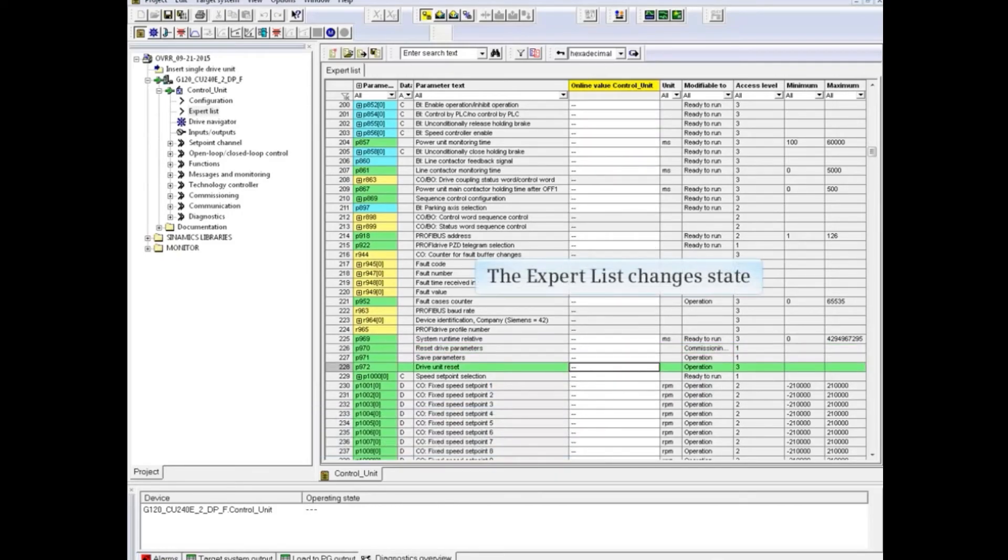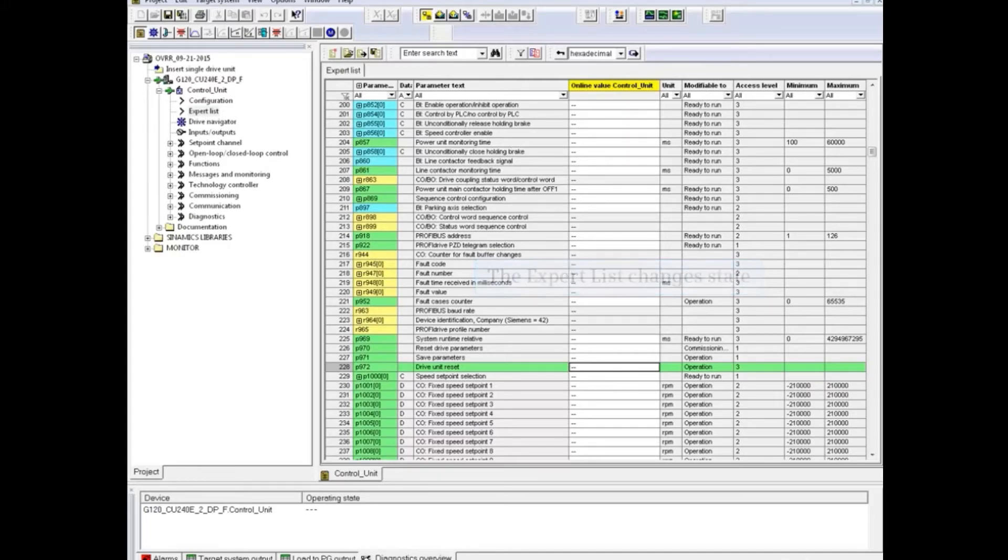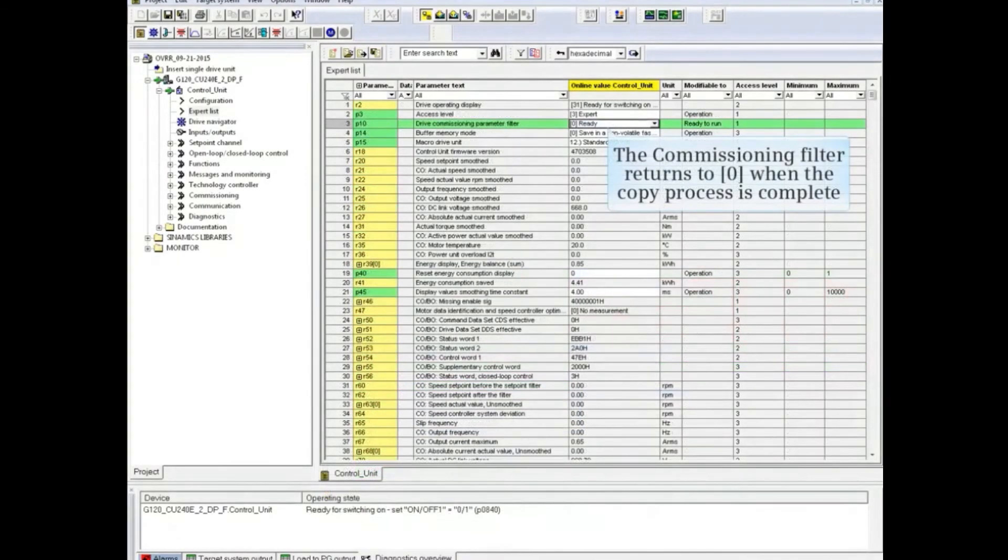The Expert List changes state. And the value at P970 returns to zero. The commissioning filter at P10 also returns to zero when the copy process is complete.